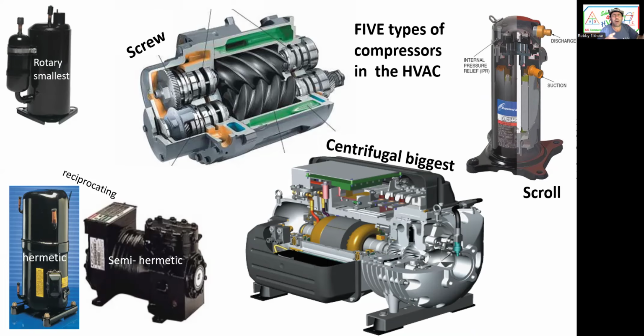Technology has advanced so much. Now they have oilless systems, no oil at all in the system, and all the electronic technology has advanced so much in this business. It's so cool. But I will do a class just about the compressors. I can talk an hour about the compressors, but for now, let's move on. We also have oil separators. The big compressors need oil separators because without oil, the compressor will burn. We need oil. So this is the oil separator. It goes between the compressor and the condenser. I just mention it here because it's part of the refrigeration cycle.